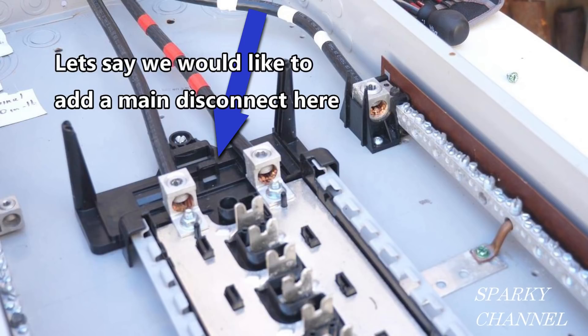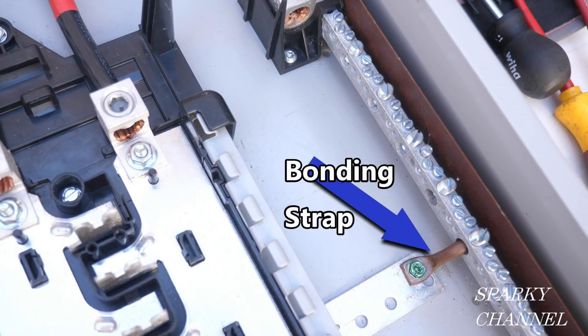In that case, we would need to bond the ground and the neutral in this panel. So we would connect the bonding strap to the neutral bar in this panel.